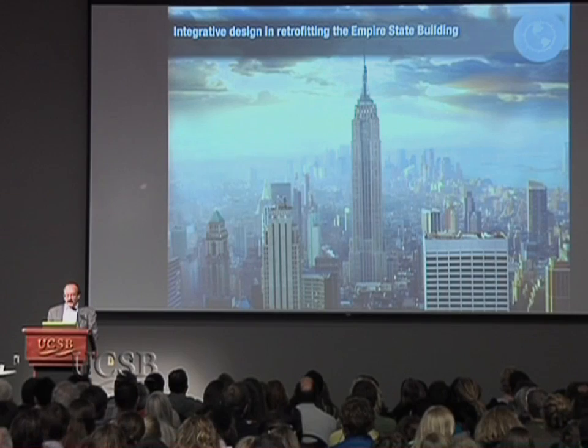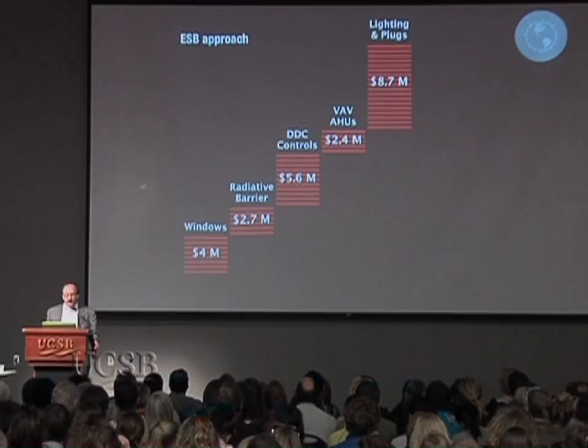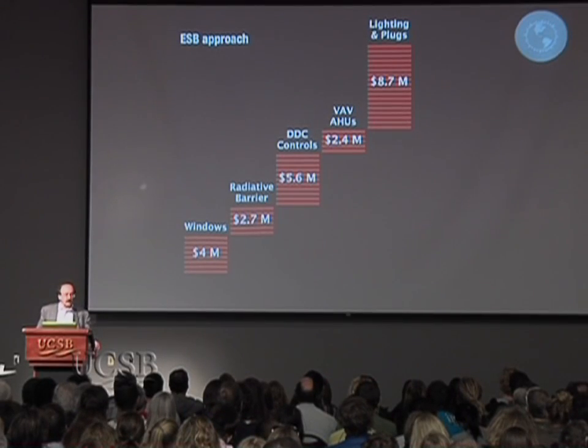Remanufacturing the 6,500 windows on site in a temporary window factory set up on a vacant floor turns them into super windows that are almost perfect in letting in light without heat. With those savings, I believe it's upwards of two-thirds of the winter heat loss and half the summer heat gain, plus better lights and office equipment and such, the peak cooling load goes down by a third.